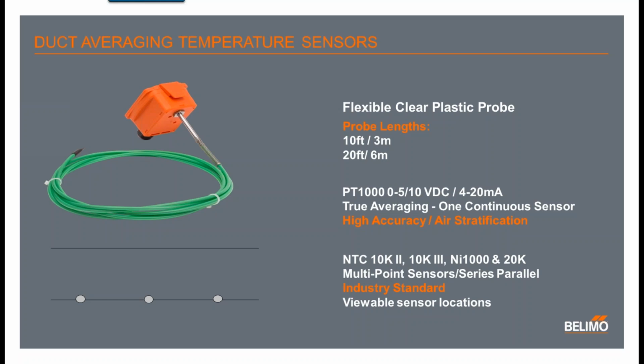Our duct averaging sensors have a flexible clear plastic probe. The probe lengths are available in 10 feet, 20 feet lengths. Our PT1000 version and also the active output versions are what we call true averaging, which has one continuous RTD sensing element which is stretched across the whole length of the probe capillary. This ensures high accuracy, and it also combats against air stratification problems. We also offer our duct averaging sensors as industry standard 10K, nickel and 20K sensors, and our clear plastic probe allows for viewable sensor locations for also combating against air stratification.